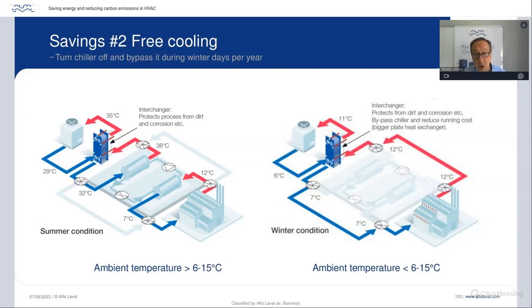In winter, when the ambient temperature is below 6 degrees Celsius, again, remember the heat exchanger is designed with a 1 degree approach. So if the cooling tower water is at 6 degrees Celsius, the heat exchanger will provide 7 degrees Celsius, which is actually the job of the chiller. So if we can get 7 degrees Celsius from the cooling tower, it means that we turn the chiller off and we provide the 7 degrees Celsius to the air handling units, the fan coils, and help cool the building during winter. So that's the double effect.